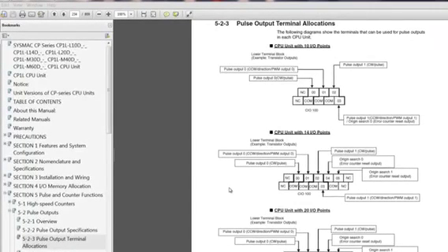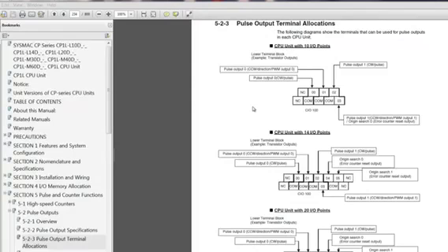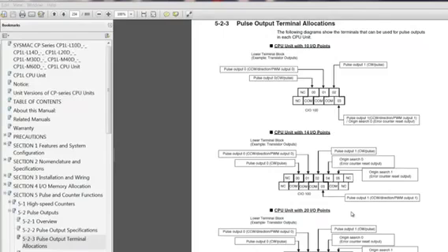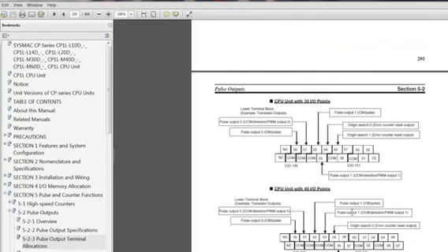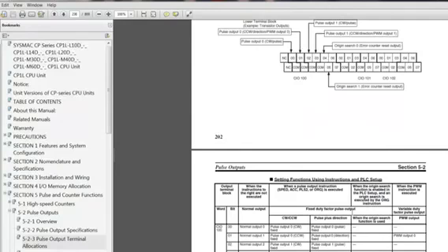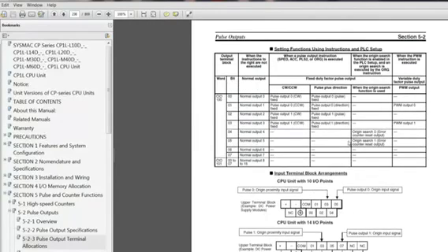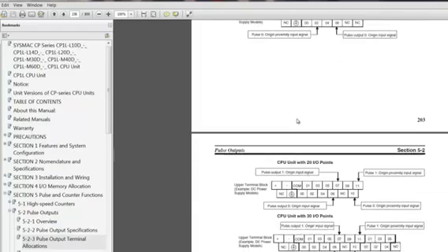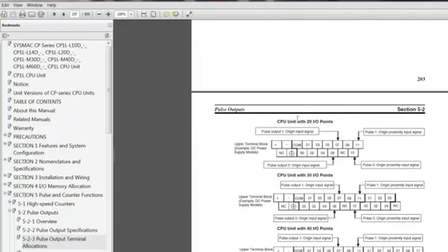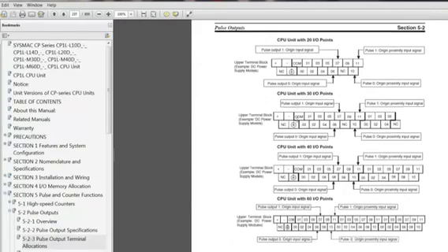In this next section, we'll review the wired interface to accomplish this. One thing to be aware of is that the I/O layout changes depending on the model that you have. So in this illustration, we're looking at a 10-point controller. You've got your pulse output capabilities labeled here. The 14-point, you'll notice that the changes as you go. If I scroll down through the locations here with regard to origin input points and so forth, to change, the table below here will show the correct locations for wiring your pulse interface, depending on if you're doing pulse and direction versus clockwise, counterclockwise. So some detail there that the programmer or the project person will need to consider.